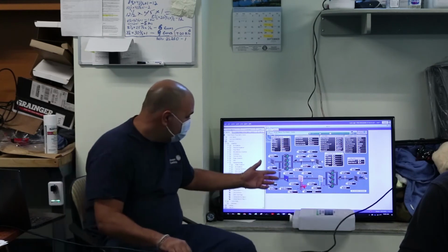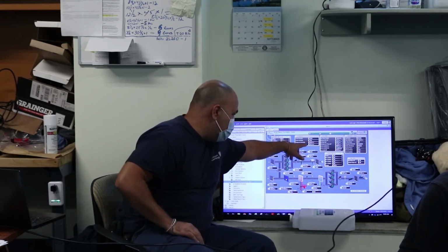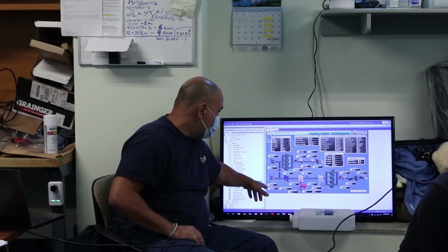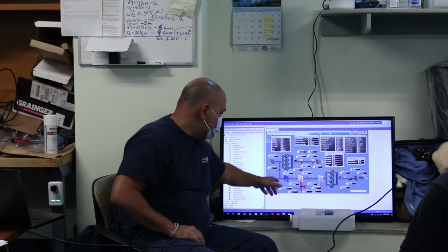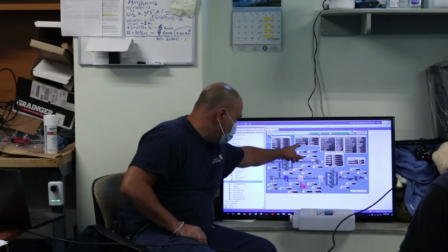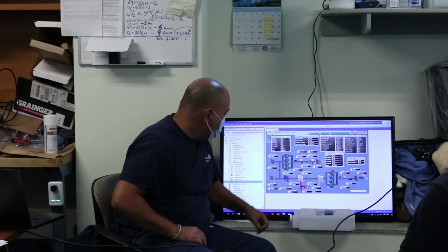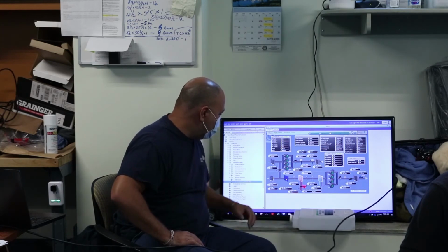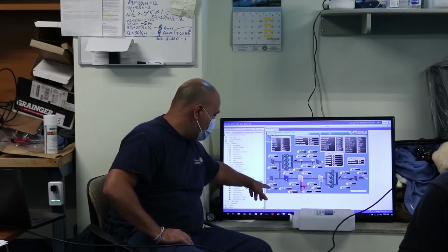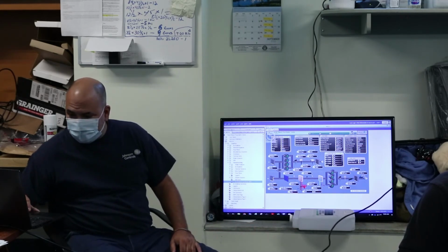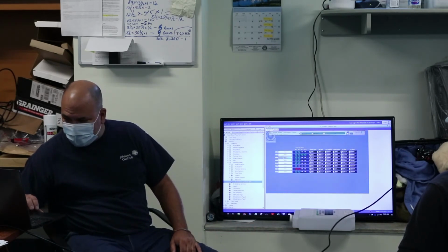So this one has the economizer available. Our first stage cooling is outside air. And it judges the economizer by whether the outside air enthalpy is lower than the return air enthalpy. So that's why you're in economizer on this one. You'll see you're doing 24,000 CFM on that. Let's see, this one may just have a hot return air coming back.